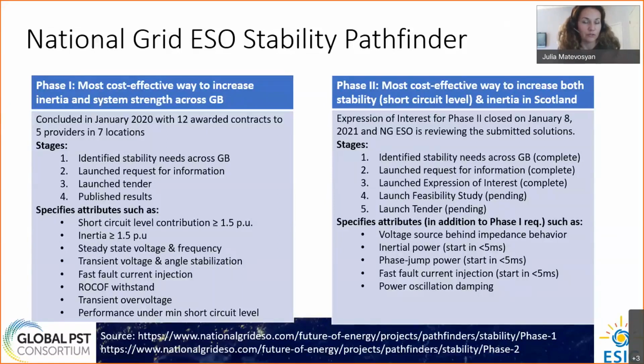For inverter-based technologies, voltage source behind impedance behavior is required. Inertial power needs to be provided within 5 milliseconds. Phase jump power, fast fault current injection, and power oscillation damping. There are more requirements; these are just additional to what was in the first stage of Pathfinder. And then also, for both Pathfinder stages, existing grid code requirements apply as well. So the solution should comply with existing grid code requirements.